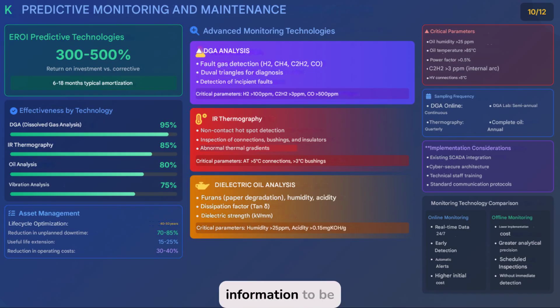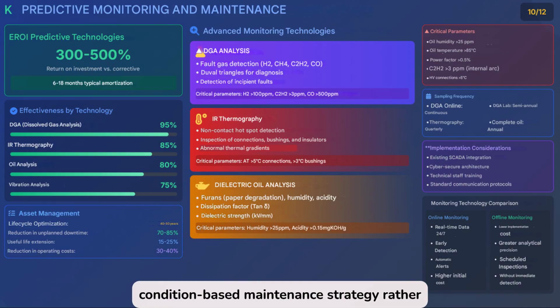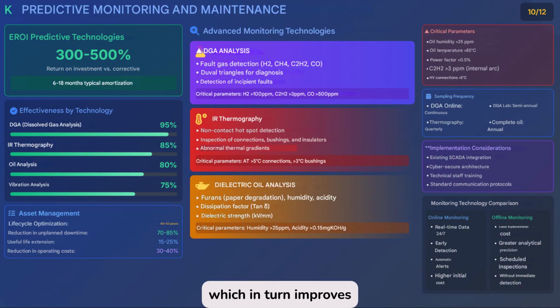However, for all this information to be useful, the frequency with which samples are taken is also key. DGA analysis can be performed continuously with online sensors or semi-annually if performed in a laboratory. Thermography is recommended quarterly, and complete oil analysis at least once a year. This periodicity allows for active monitoring without compromising operational capacity or incurring excessive costs. Furthermore, these intervals can be dynamically adjusted based on each asset's history, enabling a condition-based maintenance strategy rather than a fixed schedule, which in turn improves resource utilization and reduces unnecessary interventions.